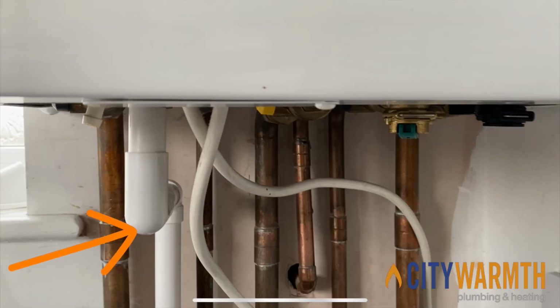Okay, so why turn the flow temperature down? The quick answer is that we turn the flow temperature down to get the boiler to condense. Does your boiler have a white plastic waste pipe on the underside of it that looks a bit like this? If so, your boiler is a condensing boiler, and we want the boiler to condense as much as possible. The more it's condensing, the more money it's saving.